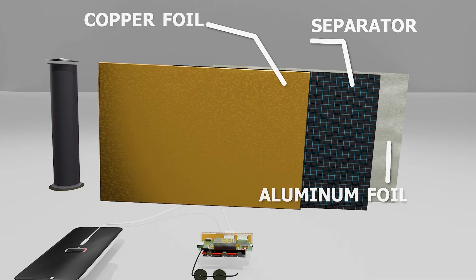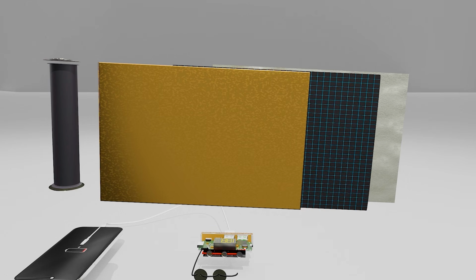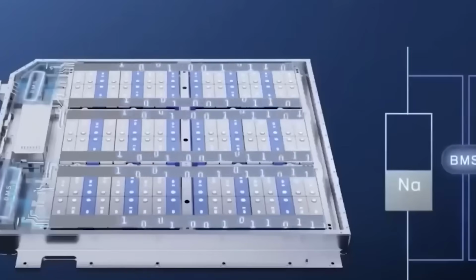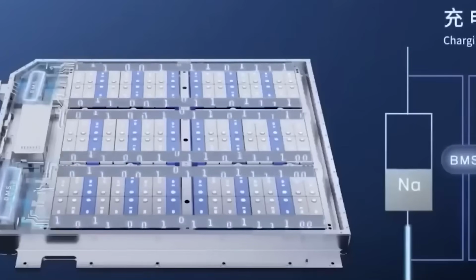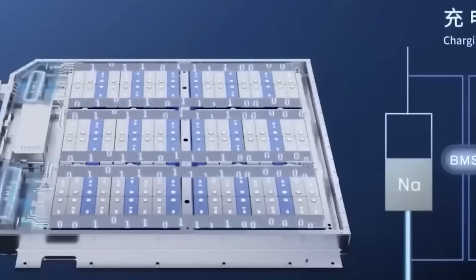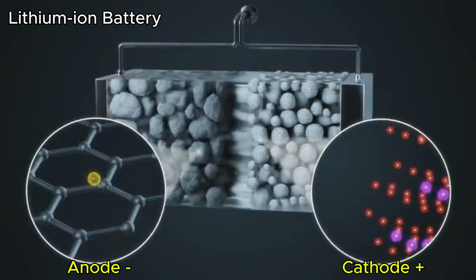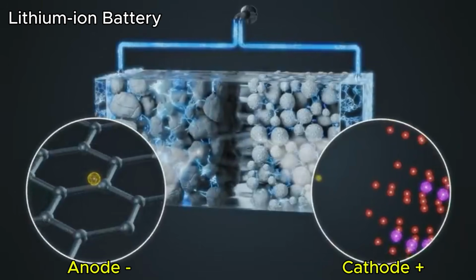Do not use a lithium BMS. The balancing algorithms, over-voltage protection thresholds, and under-voltage lockouts are calibrated for a different chemistry and will either undercharge the sodium cells or fail to protect them properly.